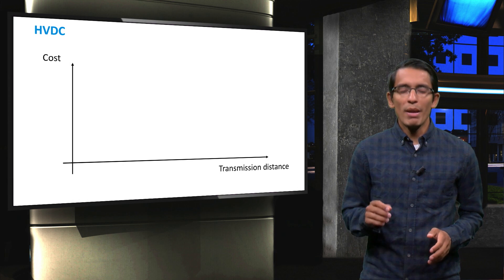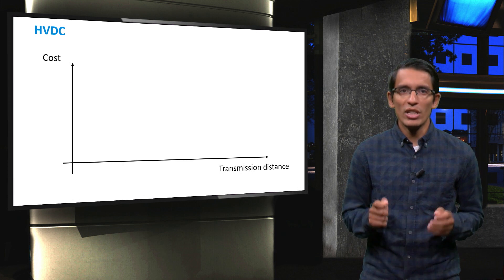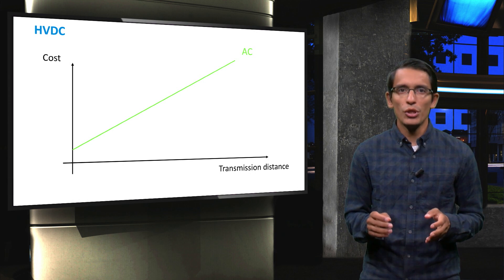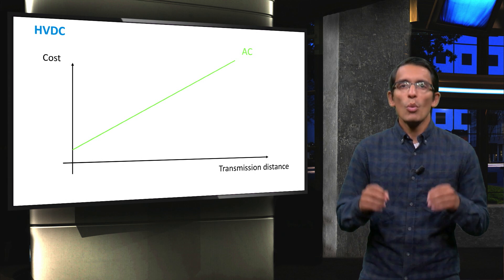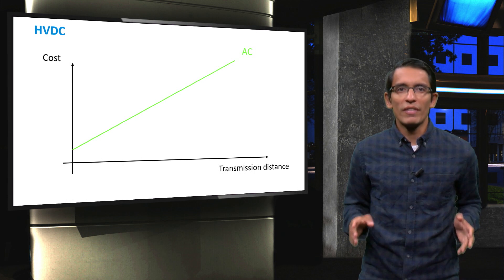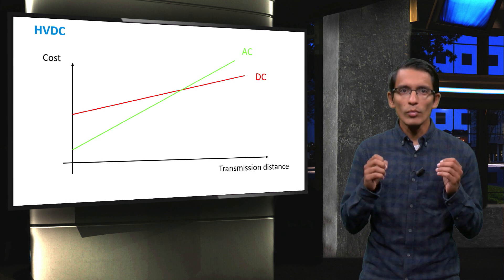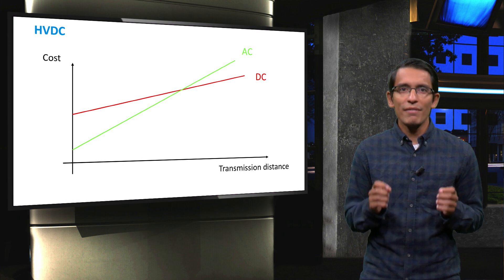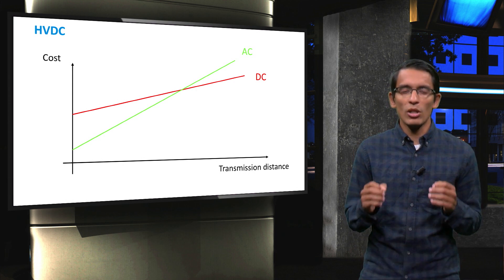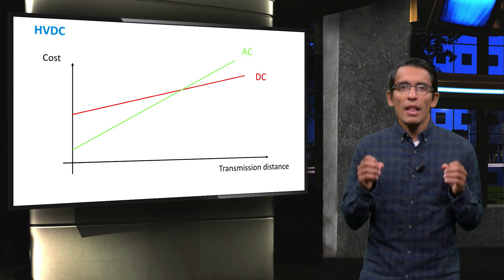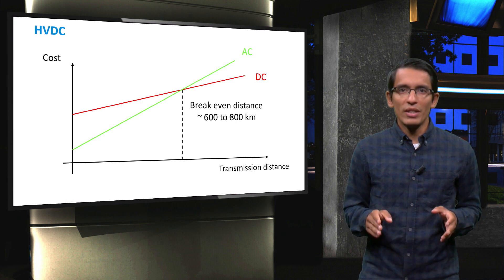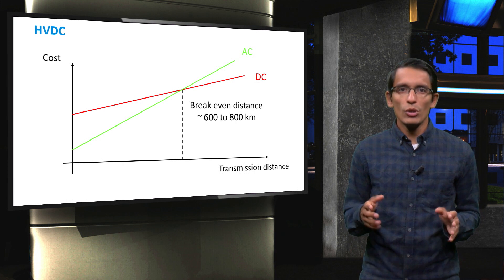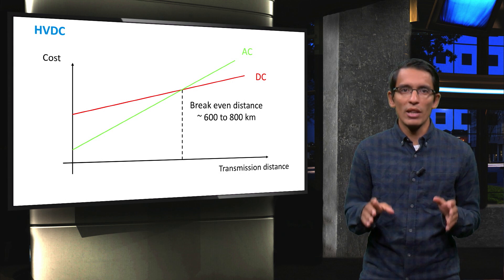It is also useful to make a comparison on the costs of AC and DC transmission. If we consider the cost of stations and lines, AC technology shows a relatively low investment cost at the beginning, which increases linearly with the amount of cables needed to cover the transmission distance. On the other hand, DC technology, shown in red on the graph, requires a high investment to set up the stations but has a lower cost per kilometer of cables. There is therefore a break-even distance after which the DC lines are cheaper than traditional AC transmission lines. This distance is usually around 600 to 800 kilometers for cables on land.